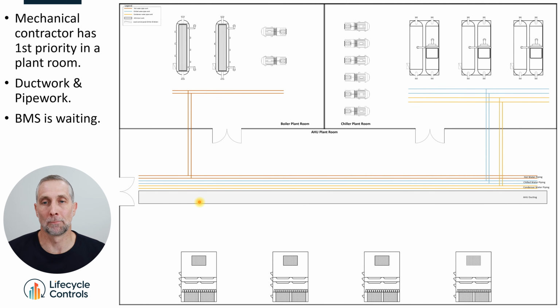And my rule of thumb generally as a project manager was that when the mechanical install was about 80% done, we would then start going in and doing some rough-in for the BMS. But through this whole part here, for the 2 or 3 months that this equipment sat in the plant rooms doing nothing, and for this first month or so that mechanical is working, the BMS is waiting. We cannot continue.